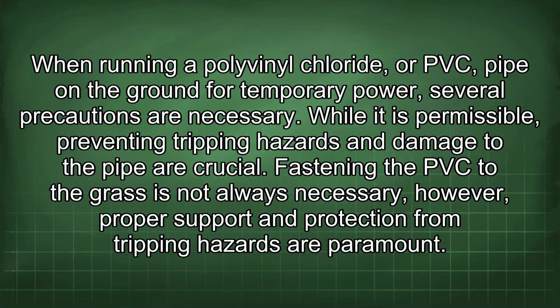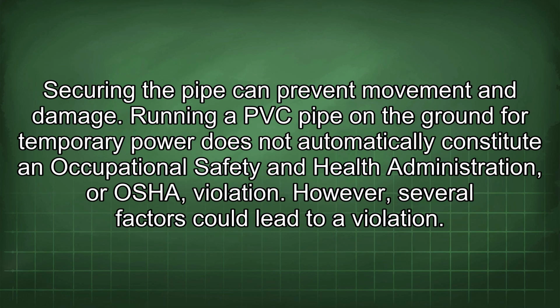When running a polyvinyl chloride, or PVC, pipe on the ground for temporary power, several precautions are necessary. While it is permissible, preventing tripping hazards and damage to the pipe are crucial. Fastening the PVC to the grass is not always necessary, however, proper support and protection from tripping hazards are paramount. Securing the pipe can prevent movement and damage.